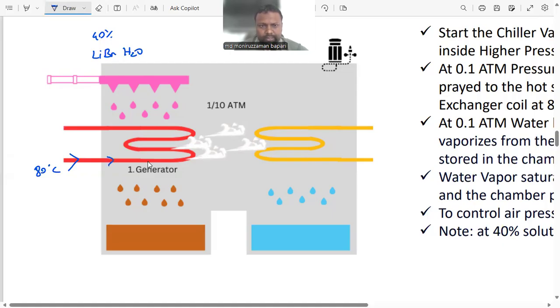Remember, pressure inside is 1/10 of atmospheric pressure. At this pressure, the boiling point of water is only 42 degrees centigrade. So the solution here is lithium bromide and water. It falls upon this heat exchanger. The temperature of this heat exchanger is 80 degrees centigrade, which is fairly above the boiling point. And in this particular scenario, water boils up and evaporates.